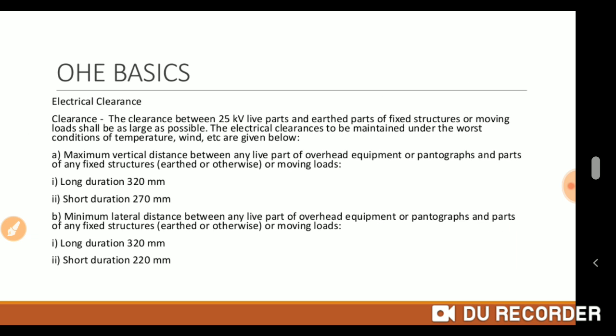Electrical clearance: the clearance between 25 kV live parts and earth parts of fixed structure or moving load shall be as large as possible. The electrical clearance to be maintained under the worst condition of temperature, wind, etc. are given below. A. Minimum vertical distance between any live part of overhead equipment or pantographs and parts of any fixed structure or moving loads: long duration 320 mm, short duration 270 mm.